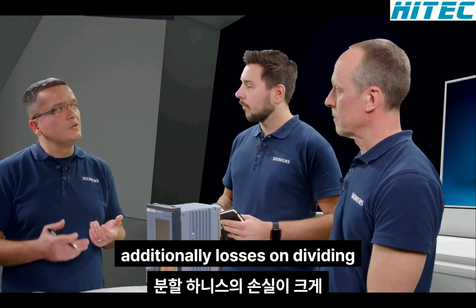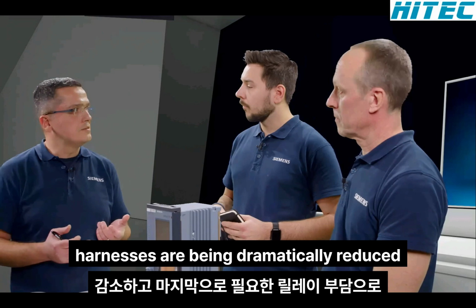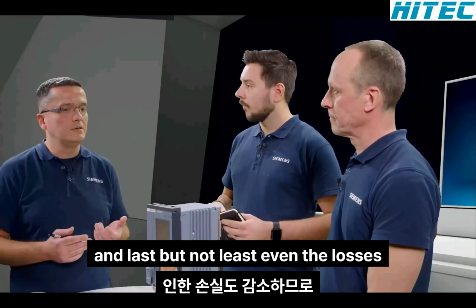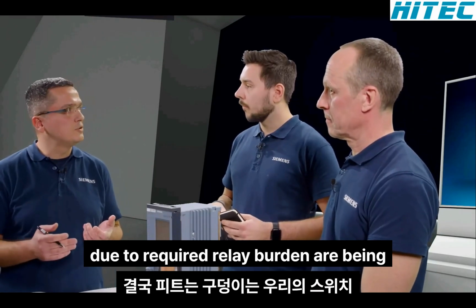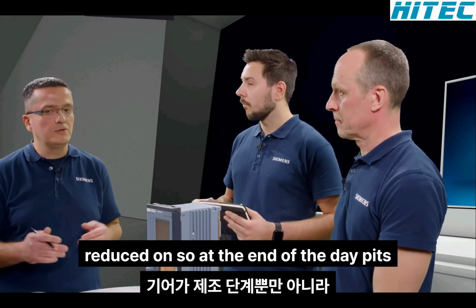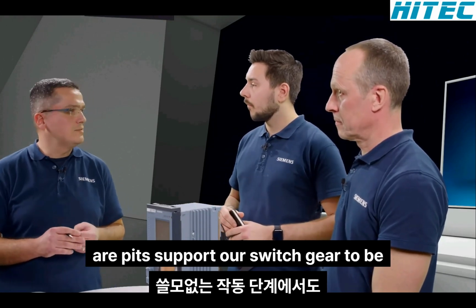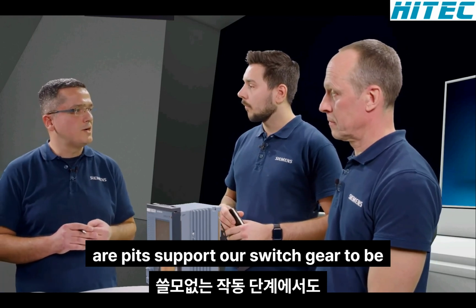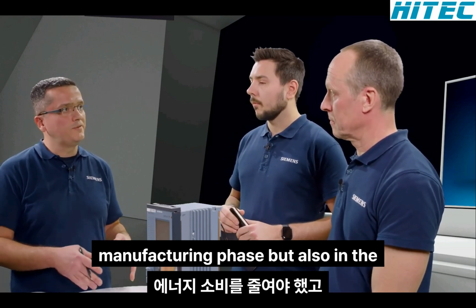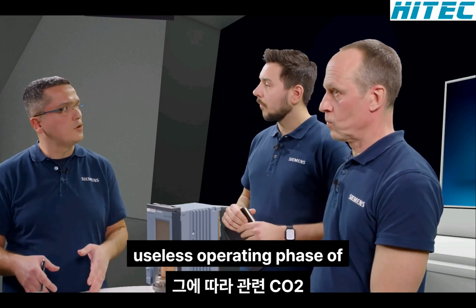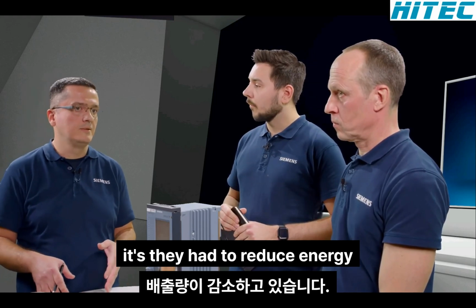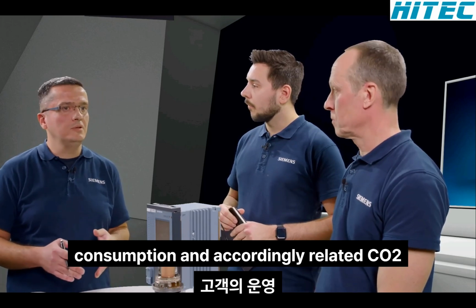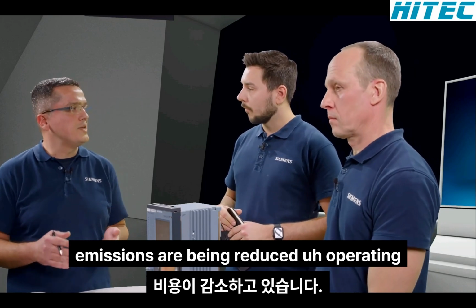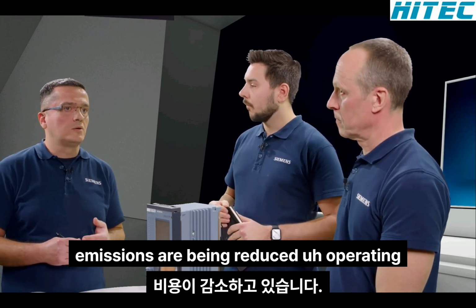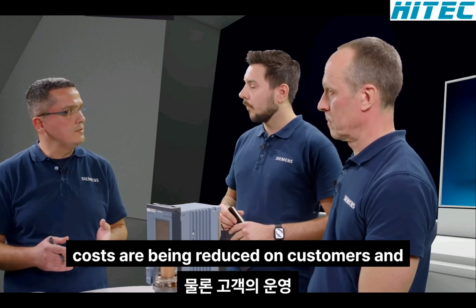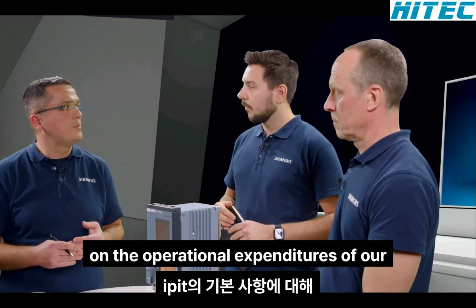Additionally, losses on the wiring harnesses are being dramatically reduced. And last but not least, even the losses due to required relay burden are being reduced. So at the end of the day, LPITs support our switchgear to be much more sustainable, not only in the manufacturing phase, but also in the operating phase. They help to reduce energy consumption, and accordingly related CO2 emissions are being reduced.